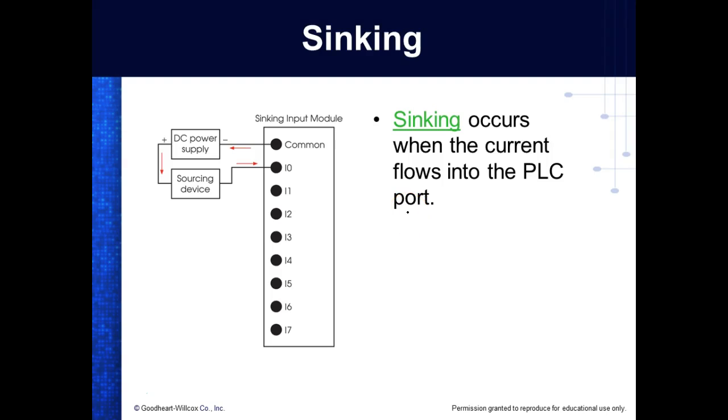So this is sinking. I've got my negative connected to the common on my module, and then my plus goes to all my devices. The 1100 that's over here, you have the ability to decide whether you want your inputs to be sinking or not.